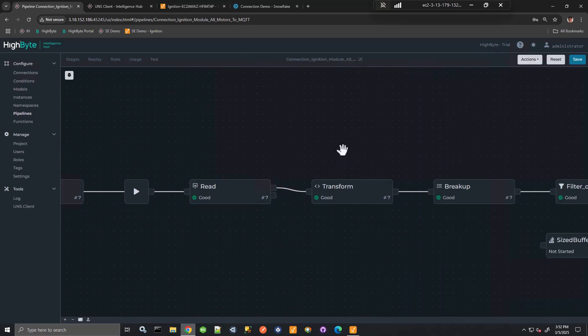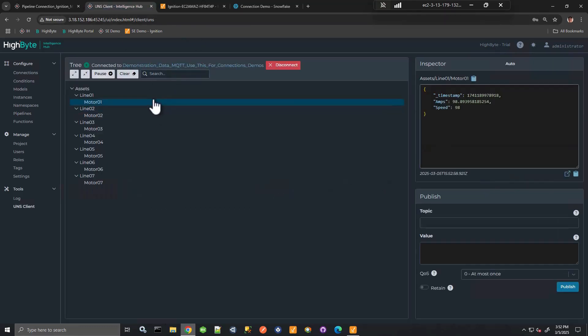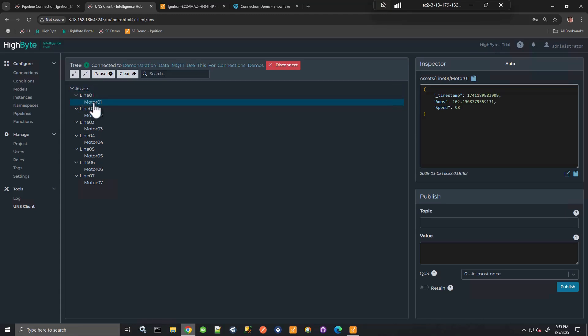I read the data from that Ignition connection input. Do some transforms, break up the array. And then I have data that's being published. In my case, to MQTT. And the hierarchy that's been defined in Ignition, I'm using to define the topic path dynamically.